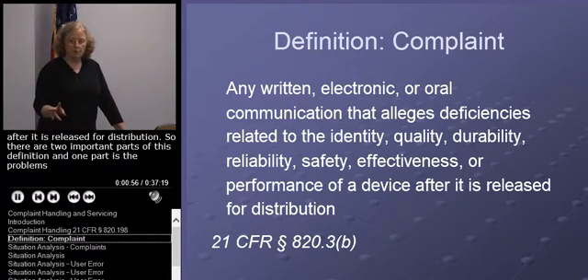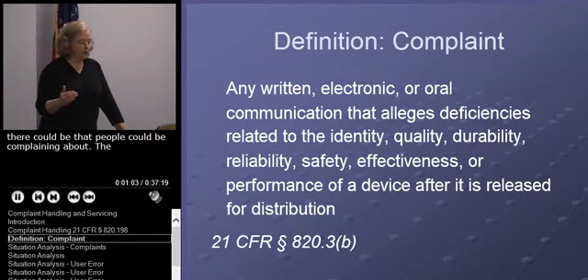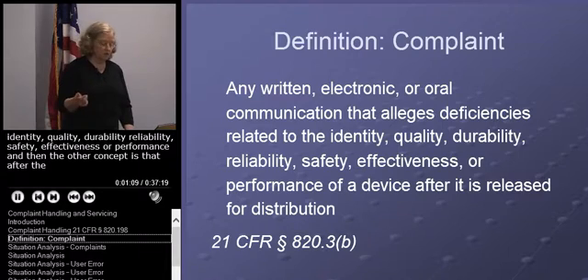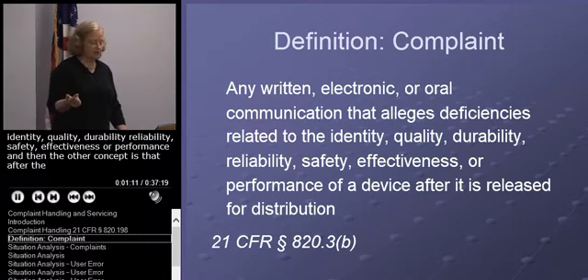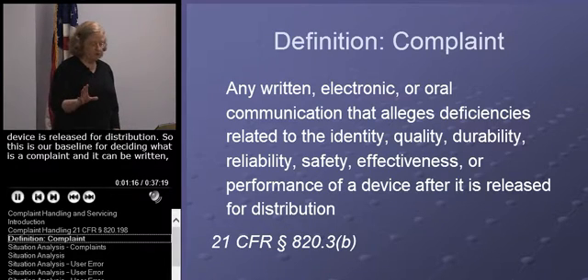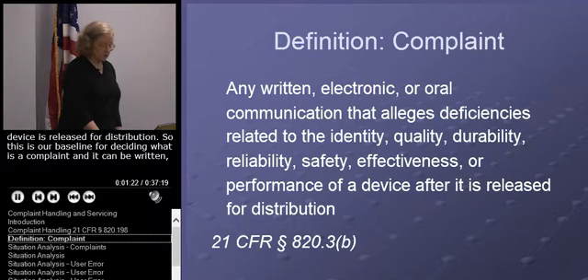There are two important parts of this definition. One part is the problems that people could be complaining about: the identity, quality, durability, reliability, safety, effectiveness, or performance. And then the other concept is that this is after the device is released for distribution. So this is our baseline for deciding what is a complaint, and it can be written, electronic, or oral.